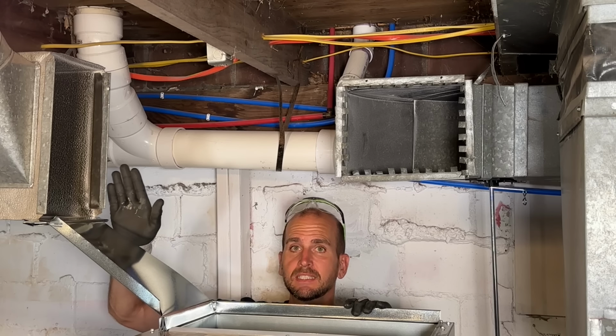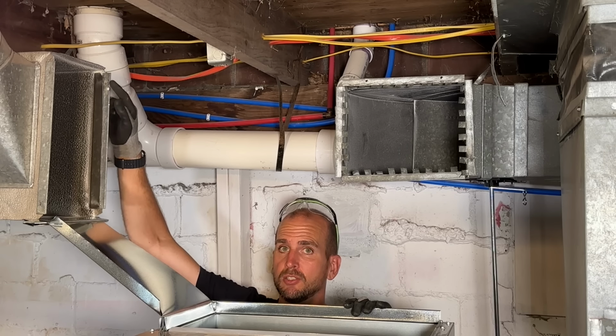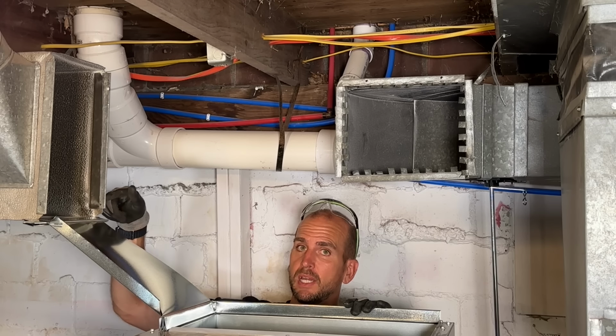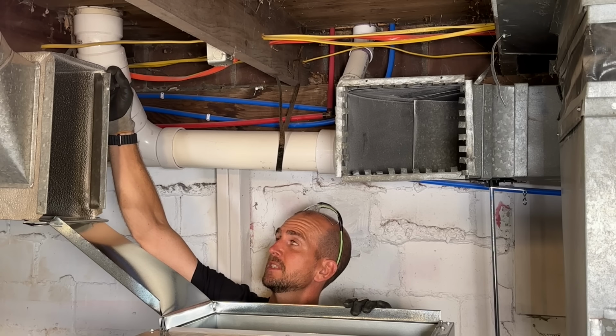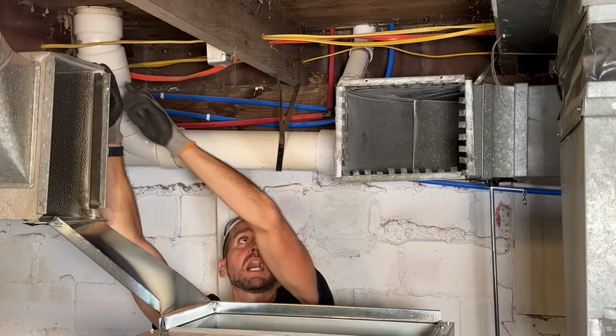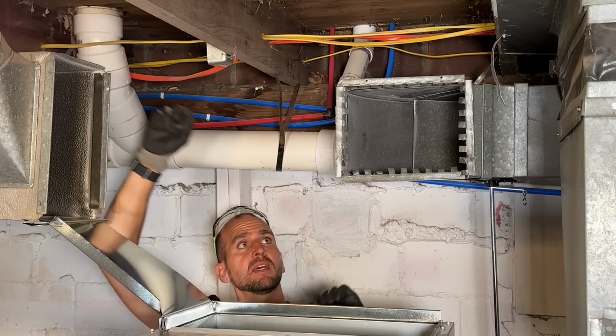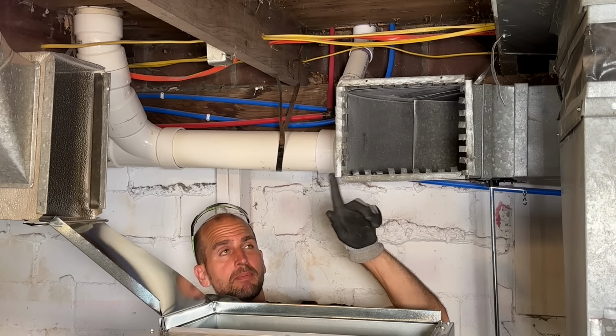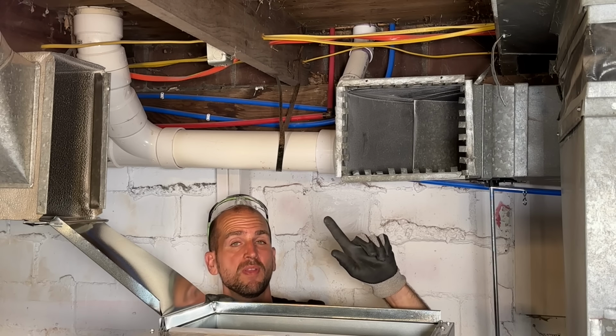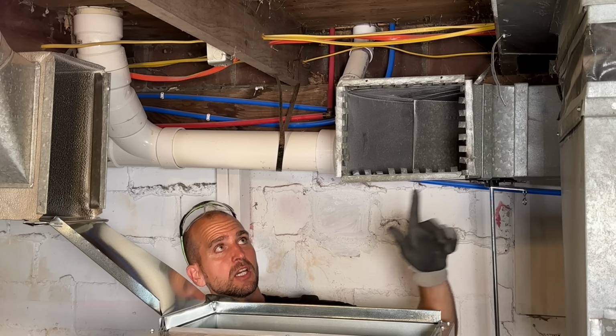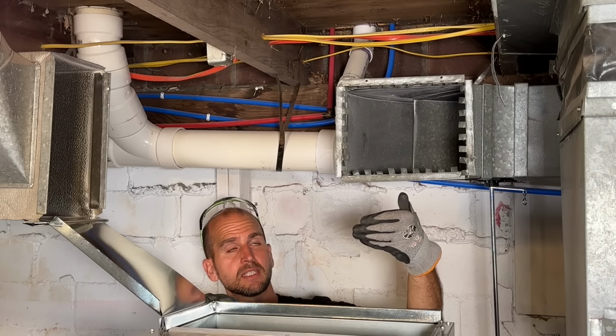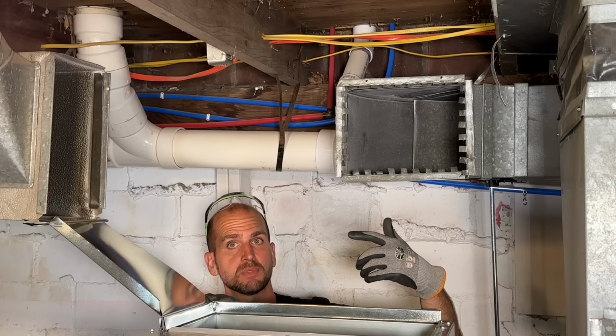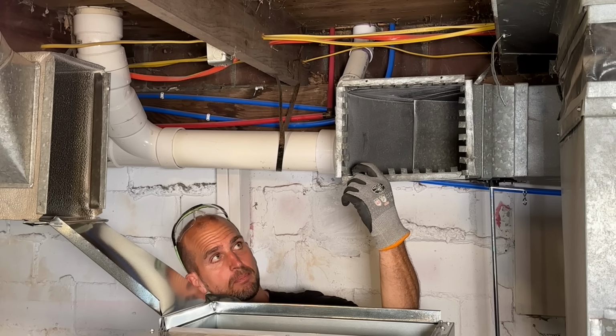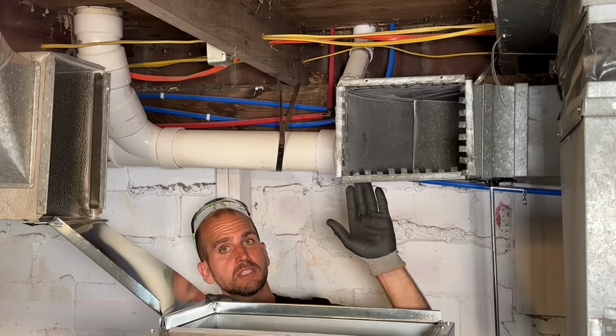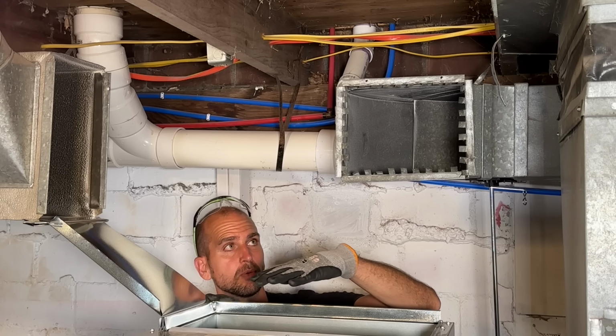Here, I'm gonna connect to the existing ductwork through this S channel. So I need 1 inch further to go into that S channel so then we can sink the screws through the S channel to secure this surface. Then I'm just gonna have a straight edge to the top all the way across here for the full length. And I have an old ductwork attachment mechanism with all these little tabs. So what that means is I'm gonna have to cut out this ductwork hole, and then from the inside, and that's where the order of operations comes in, because I need full access to the inside, I gotta bend each one of these tabs over to secure this ductwork into this custom piece that we're making.